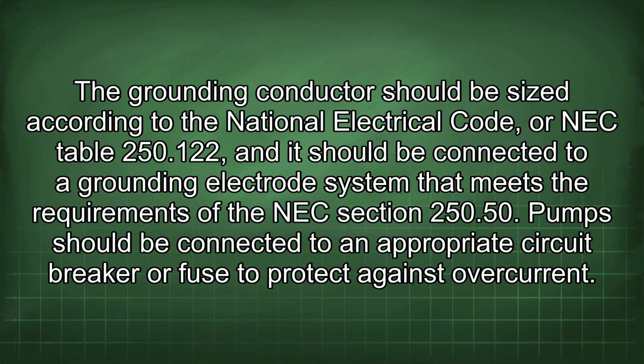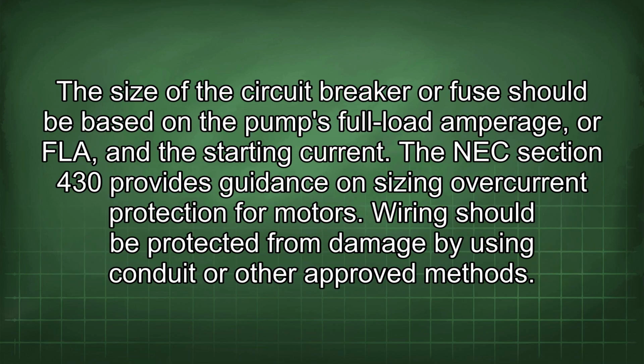The grounding conductor should be sized according to the National Electrical Code, or NEC, Table 250.122, and it should be connected to a grounding electrode system that meets the requirements of NEC Section 250.50. Pumps should be connected to an appropriate circuit breaker or fuse to protect against overcurrent. The size of the circuit breaker or fuse should be based on the pump's full load amperage, or FLA, and the starting current. NEC Section 430 provides guidance on sizing overcurrent protection for motors.